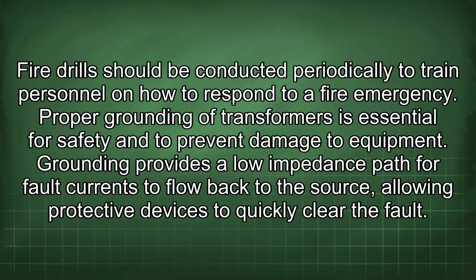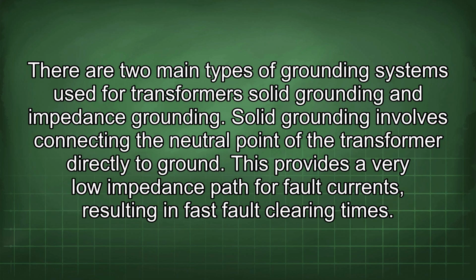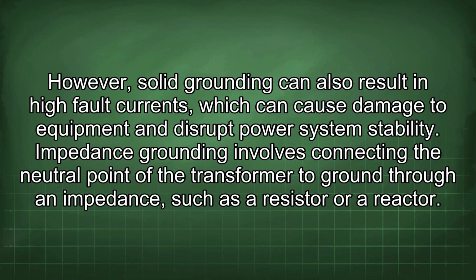Proper grounding of transformers is essential for safety and to prevent damage to equipment. Grounding provides a lower impedance path for fault currents to flow back to the source, allowing protective devices to quickly clear the fault. There are two main types of grounding systems used for transformers: solid grounding and impedance grounding. Solid grounding involves connecting the neutral point of the transformer directly to ground. This provides a very low impedance path for fault currents, resulting in fast fault clearing times. However, solid grounding can also result in high fault currents, which can cause damage to equipment and disrupt power system stability.